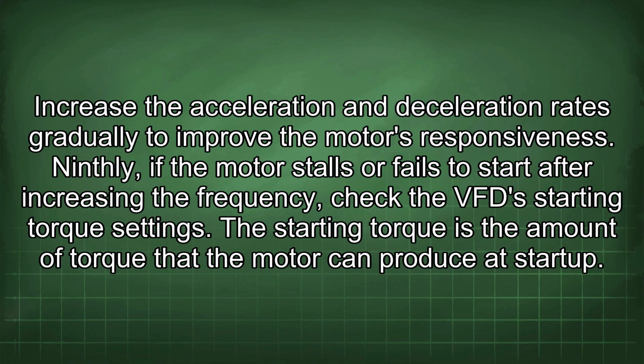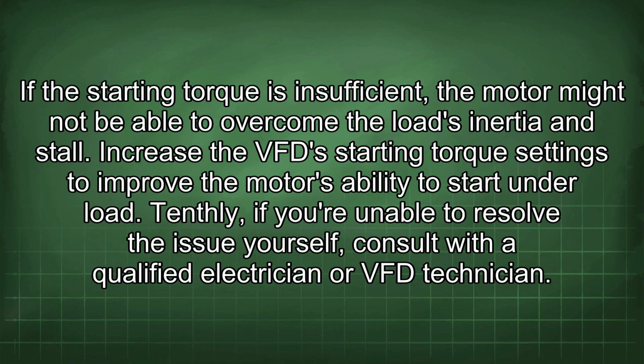Ninthly, if the motor stalls or fails to start after increasing the frequency, check the VFD starting torque settings. The starting torque is the amount of torque that the motor can produce at startup. If this starting torque is insufficient, the motor might not be able to overcome the load's inertia and stall.